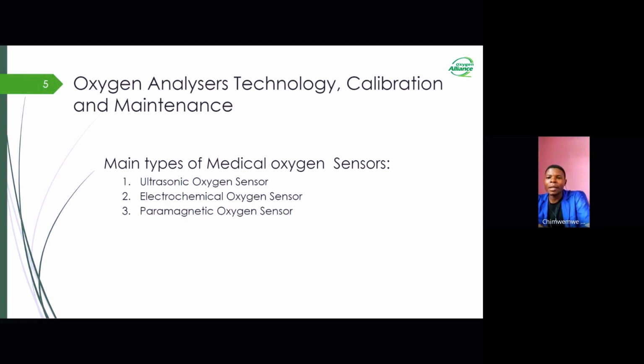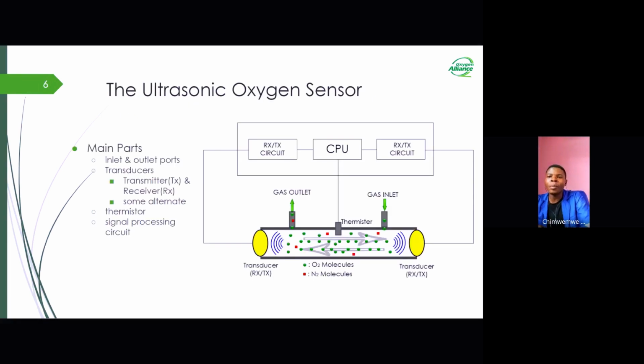Moving on, I'll first talk about the ultrasonic oxygen sensor. The ultrasonic oxygen sensor consists of four main parts or components. The first is the inlet and outlet ports that allow the gas to flow through. You can see that in the graphics to your right. Then there are ultrasonic transducers located at either end of the sensor. These transducers send out and receive ultrasonic sound waves. In some sensors, there is a separate part for sending and another for receiving, while in others, they take turns in doing both jobs.